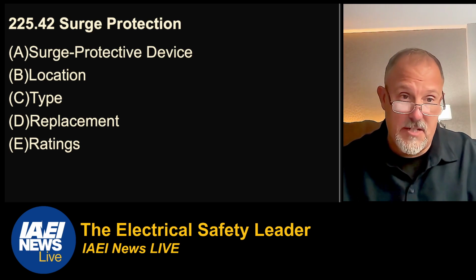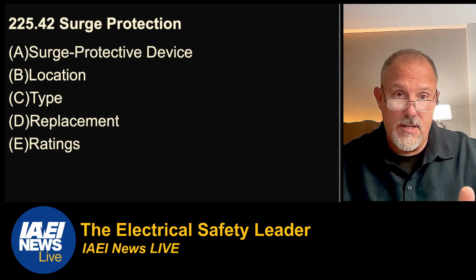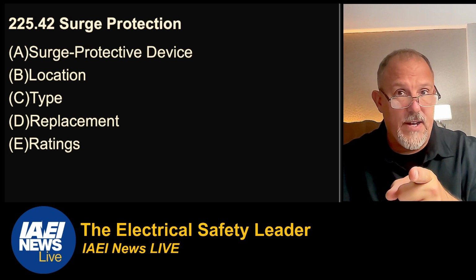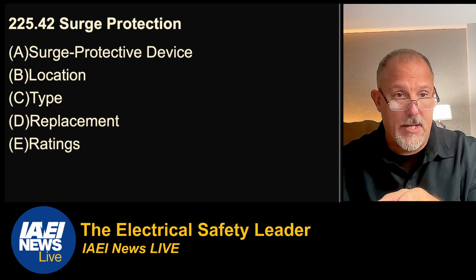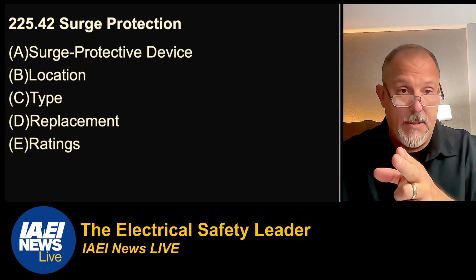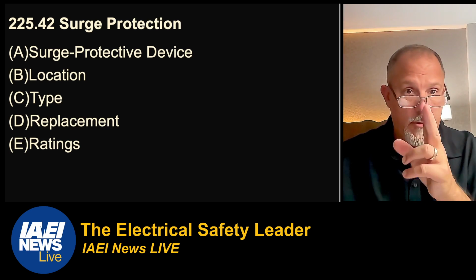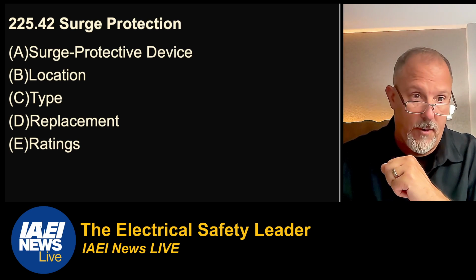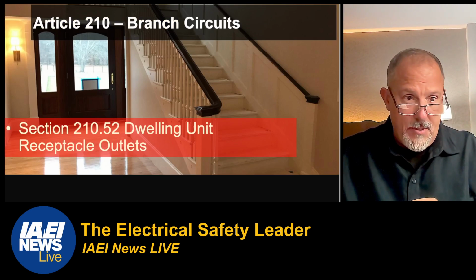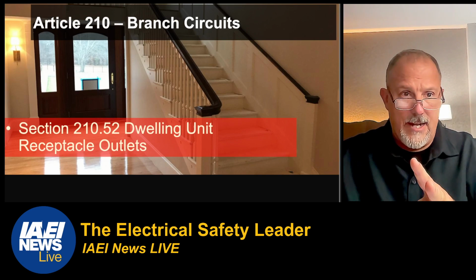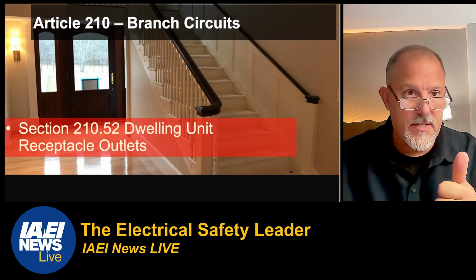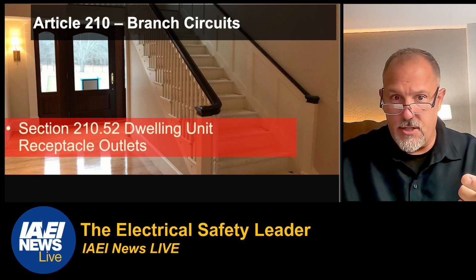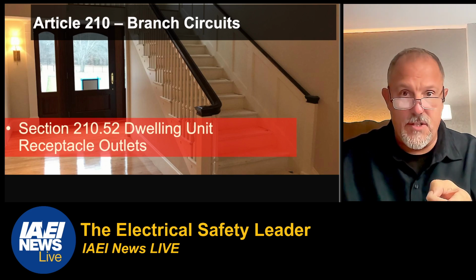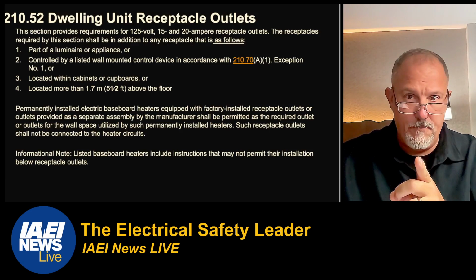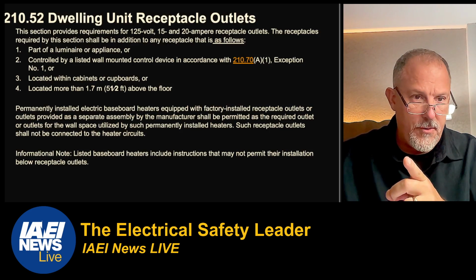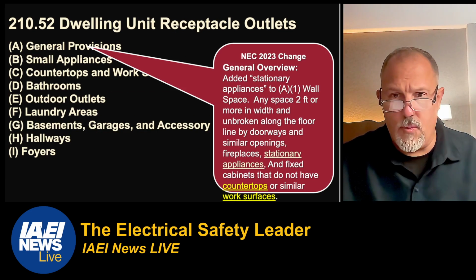So surge saw some expansion beyond dwelling units, but the 225 and the 215 is going to impact your dwelling unit applications, very well could impact the dwelling unit applications. So look at that 215 and 225 requirements. Now, I believe this is the second to last item, and we're almost done. So this is a big change, I think. 210.52, branch circuits.